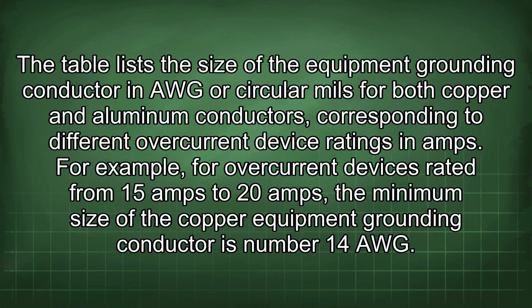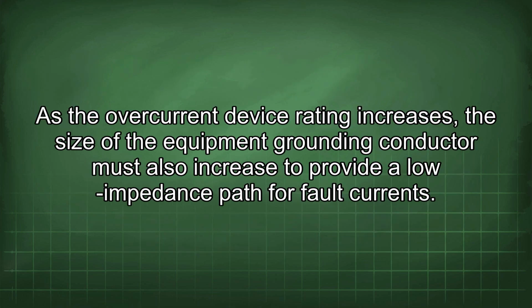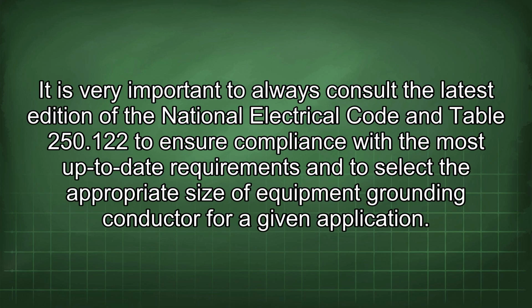For example, for overcurrent devices rated from 15 amps to 20 amps, the minimum size of the copper equipment grounding conductor is number 14 AWG. As the overcurrent device rating increases, the size of the equipment grounding conductor must also increase to provide a low impedance path for fault currents. It is very important to always consult the latest edition of the National Electrical Code and Table 250.122 to ensure compliance with the most up-to-date requirements and to select the appropriate size of equipment grounding conductor for a given application.